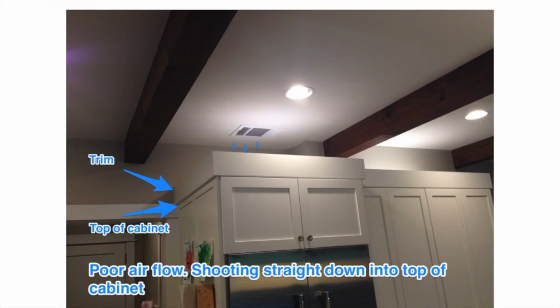This is a picture of poor design. The HVAC company put their vent above a cabinet, and they probably didn't realize at the time that the cabinet was going to be so high, but in this particular case the homeowner was complaining of lack of airflow in their kitchen, and the reason for it is all of the air was being caught and kept up above their cabinetry. So I recommended to them that they most likely need to move that duct to a more central location where it can be more useful.